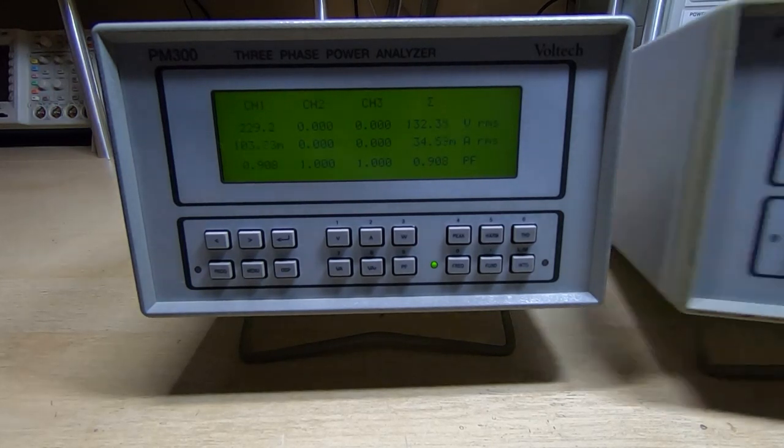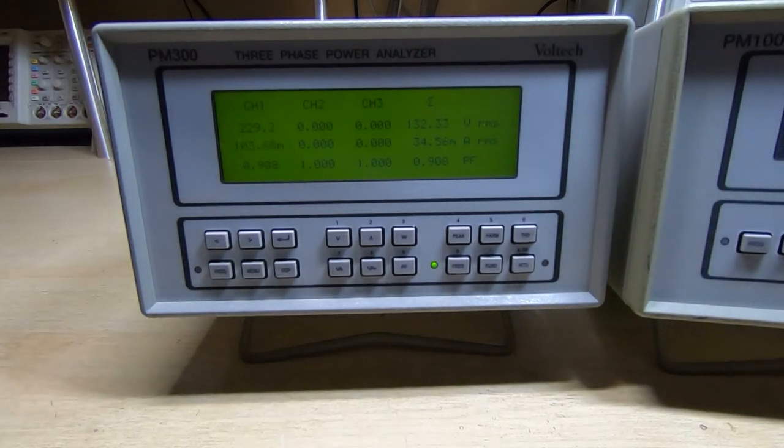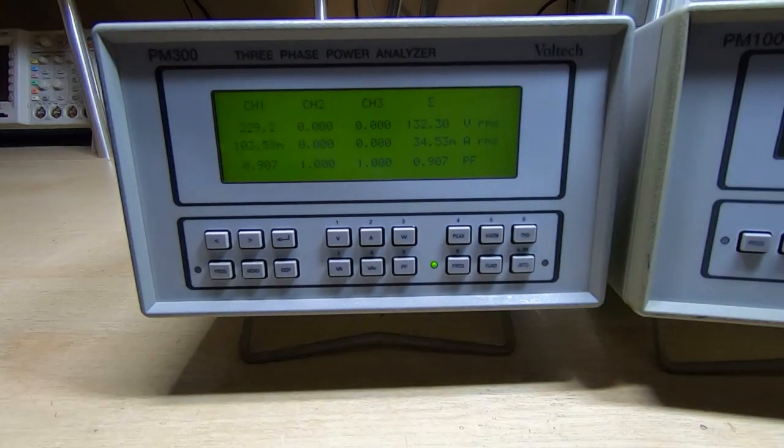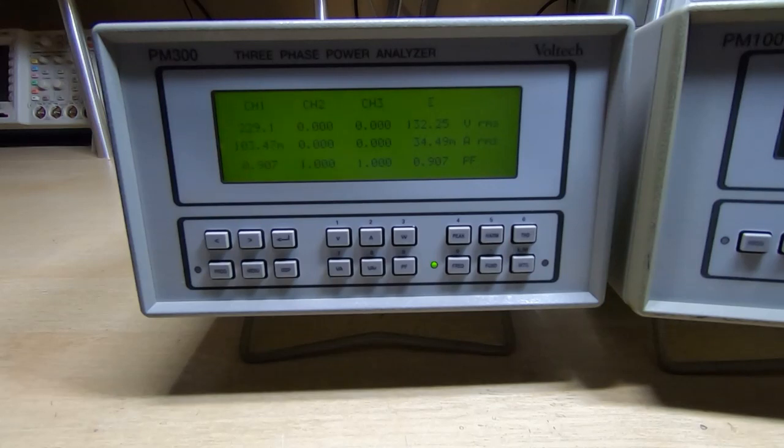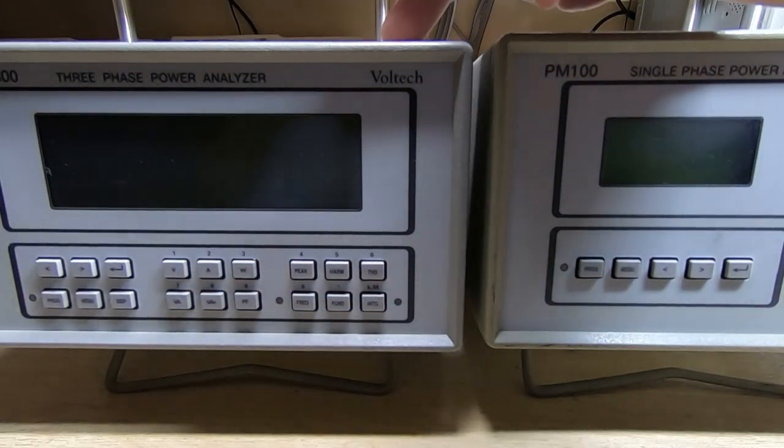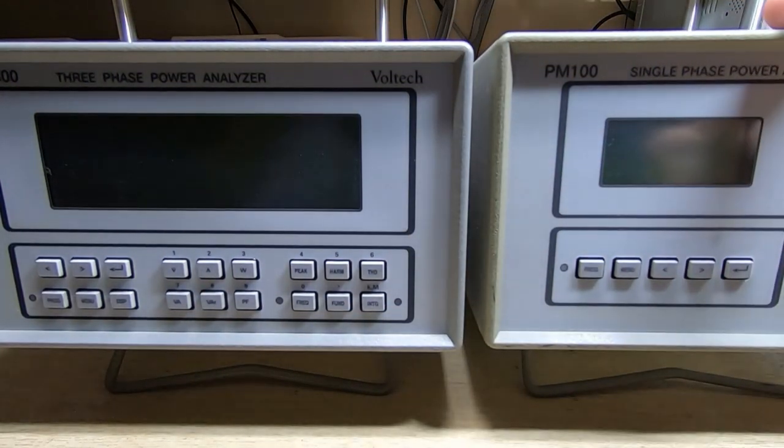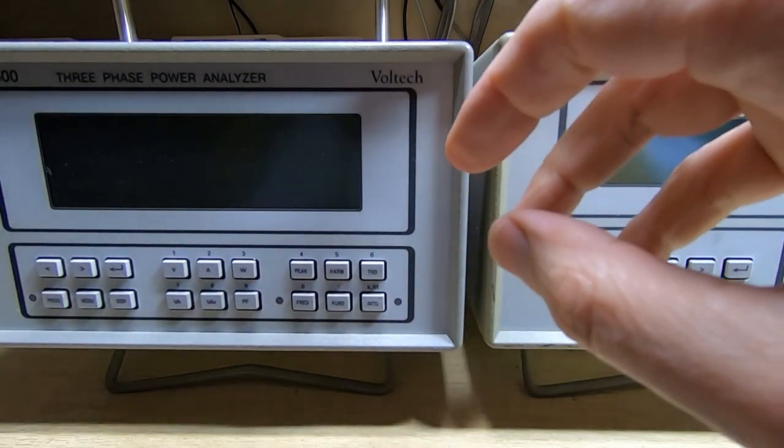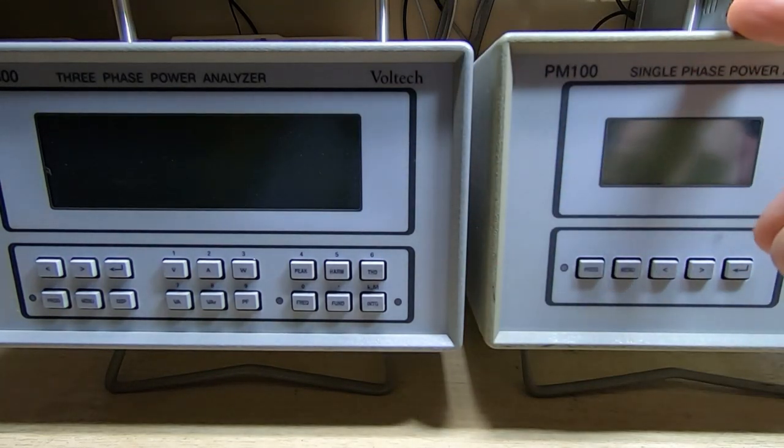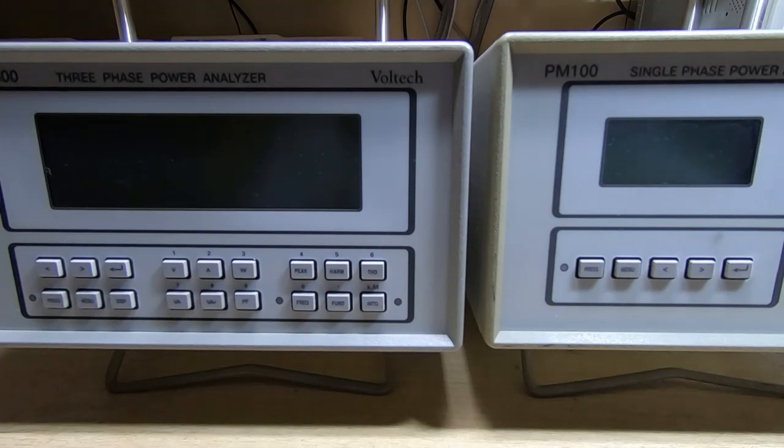What we can now do of course is also plug in the PM100 and have them both monitored by the PM300. So I'll do that and we'll see what results we get. I now have both the PM300 and the PM100 being monitored by the 300. The PM300 is on channel 1, the PM100 is on channel 2, so I'll power it up and we'll see what results we get.